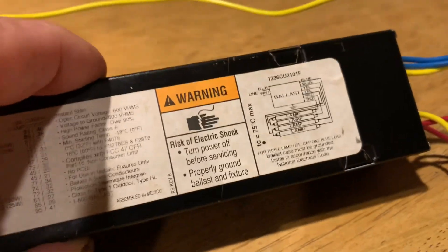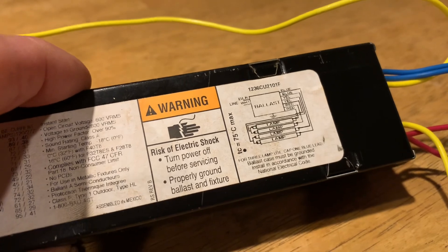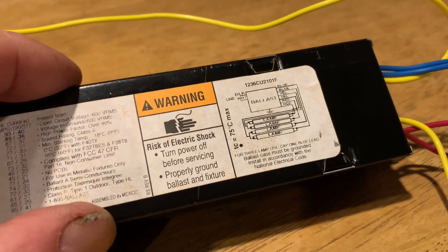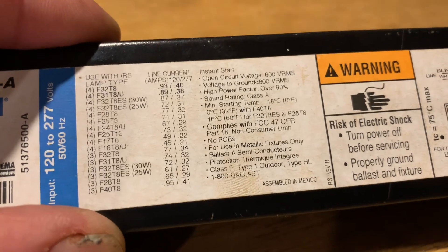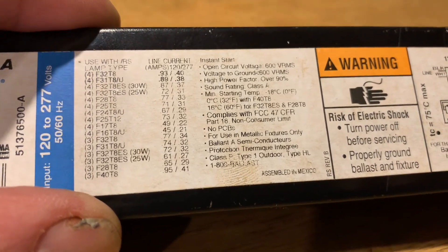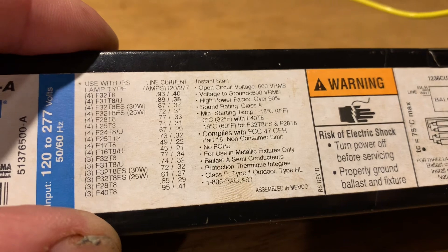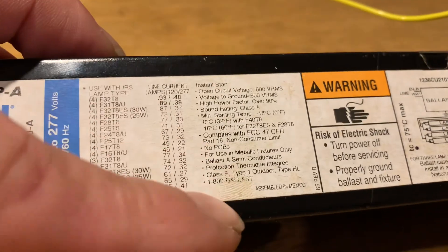You don't need an actual ground wire on this piece because it is mechanically fastened to the housing. Of course, they say properly ground the ballast and fixture, and turn off power before servicing. They have all the specs here — line current, amps, voltage, open circuit voltage, RMS, power frequency, power factor, sound rating Class A, minimum starting temperature, and all the compliance information. For use in metallic fixtures only — remember that.